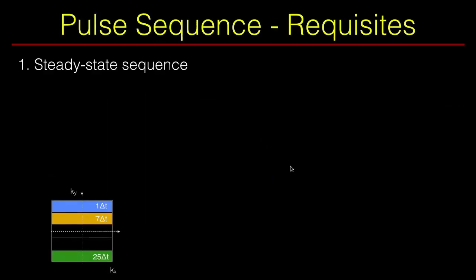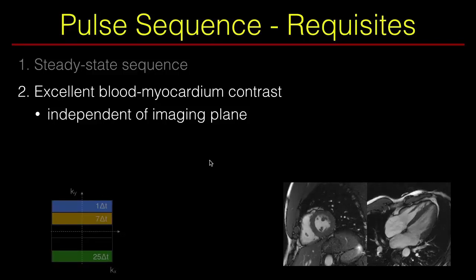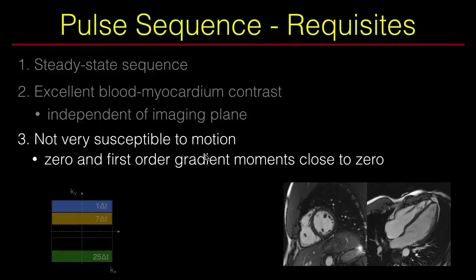With this reconstruction technique in mind, how do we design a cardiac cine sequence? We combine data acquired at different time points, so we need a steady-state sequence. We acquire images in different imaging planes, so we need bright blood and dark myocardial signal — good contrast independent of imaging plane. There is both blood flow and myocardial motion, so we need a sequence not susceptible to flow and motion; the zeroth and first order gradient moments should be close to zero.